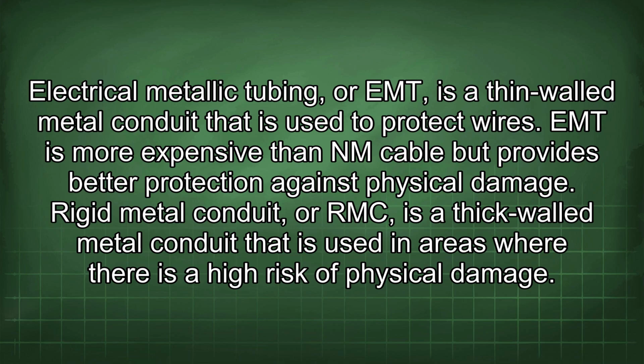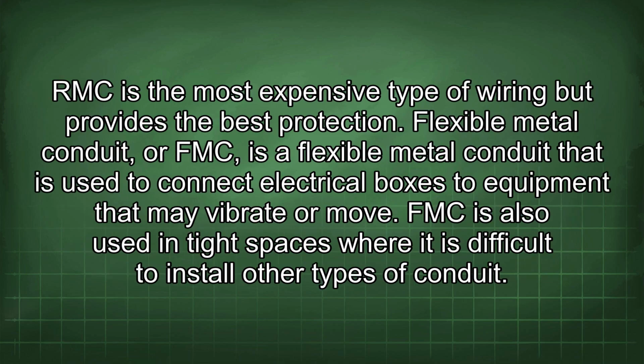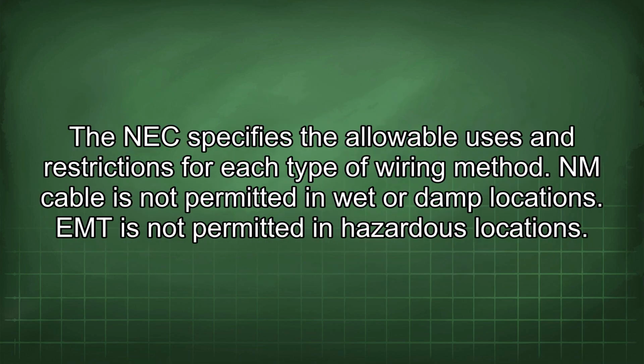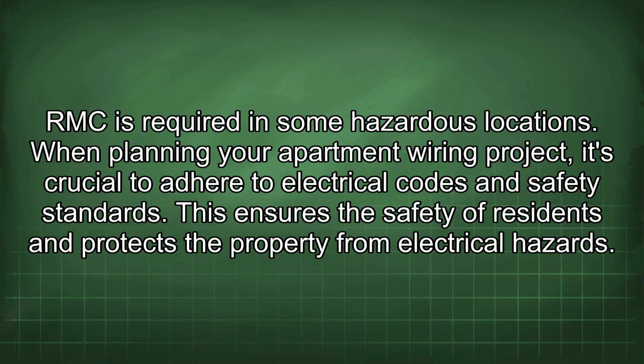Rigid metal conduit, or RMC, is a thick-walled metal conduit that is used in areas where there is a high risk of physical damage. RMC is the most expensive type of wiring but provides the best protection. Flexible metal conduit, or FMC, is a flexible metal conduit that is used to connect electrical boxes to equipment that may vibrate or move. FMC is also used in tight spaces where it is difficult to install other types of conduit. The NEC specifies the allowable uses and restrictions for each type of wiring method. NM cable is not permitted in wet or damp locations. EMT is not permitted in hazardous locations. RMC is required in some hazardous locations.